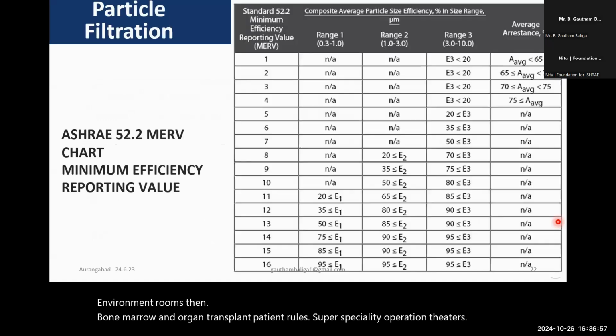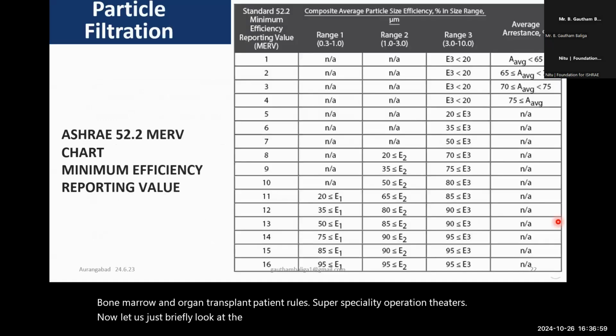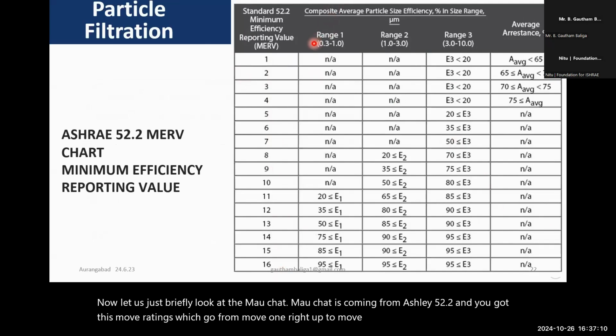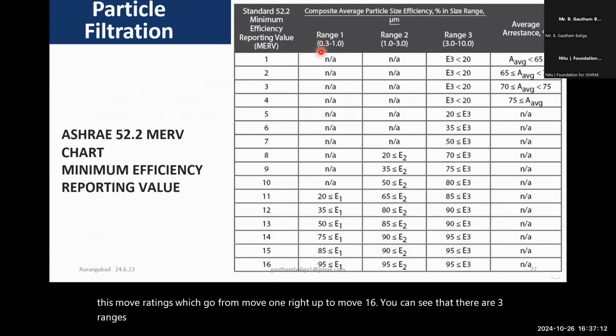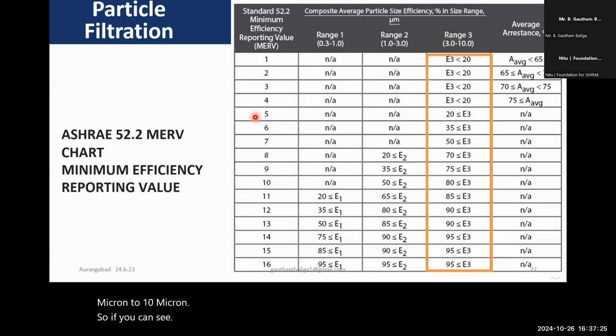Now, let us just briefly look at the MERV chart. MERV chart is coming from ASHRAE 52.2, and you've got these MERV ratings which go from MERV 1 right up to MERV 16. You can see that there are three ranges. Range 1 is 0.3 micron to 1 micron. Range 2 is 1 micron to 3 micron. Range 3 is 3 micron to 10 micron. So if you can see, MERV 1 right up to MERV 16 can do filtration to various efficiencies for 3 to 10 micron.